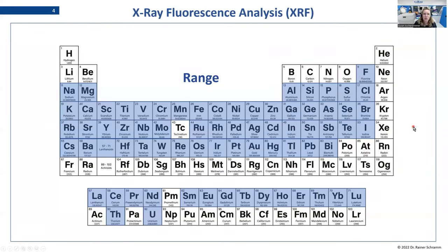What is the range that we can measure with X-ray fluorescence analysis? A rule of thumb is that we can measure from fluorine to uranium as the heaviest element. There are special options where you can also measure lighter elements up to boron, but that requires a lot of extra effort. Generally, for most devices it starts with fluorine, and for some devices it starts with sodium or magnesium, depending on the configuration of your device.